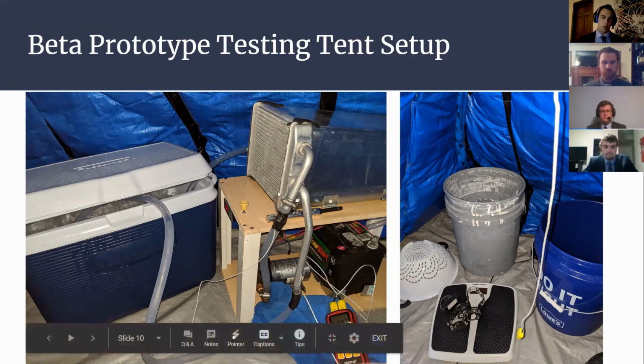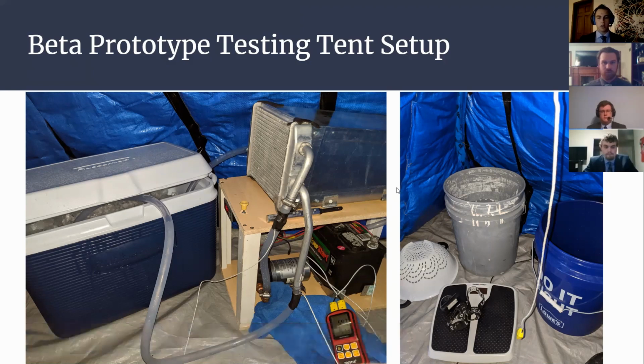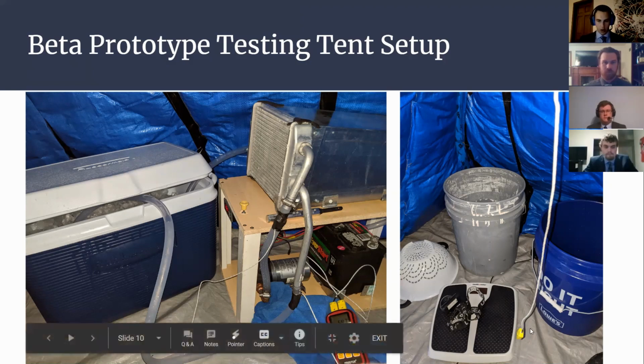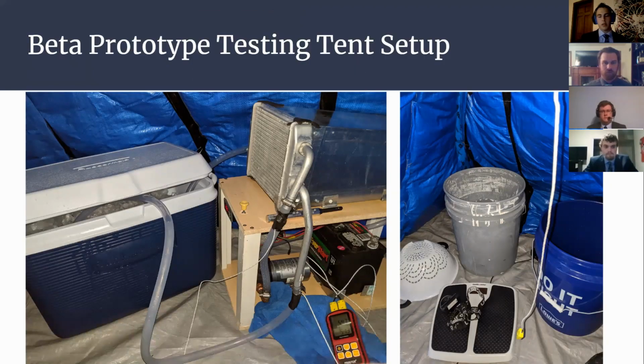You can see the thermocouple wires measuring the inlet and outlet water temperatures into the heater core. And then this white wire up here for the thermocouple goes to the top of the tent outside, and that just takes the ambient conditions on the outside of the tent. And as you can see, the 5-gallon buckets in there were how we weighed the ice. We had to throw the ice in there, weigh myself with the ice, and then weigh myself with empty buckets on that scale, and that's how we did that as well.